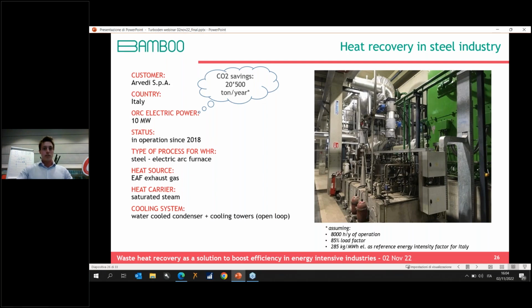It uses saturated steam as a thermal vector from the electric arc furnaces, and this is a very particular example of the flexibility of the ORC unit, as Tommaso was explaining to you before, because typically electric arc furnace process is not stable. It is composed of 2 main stages, power on and power off.